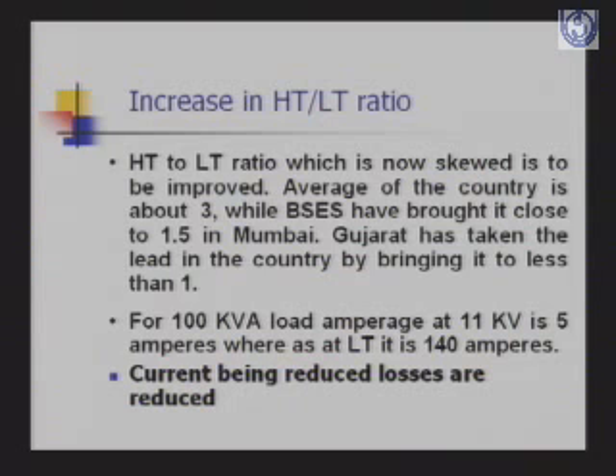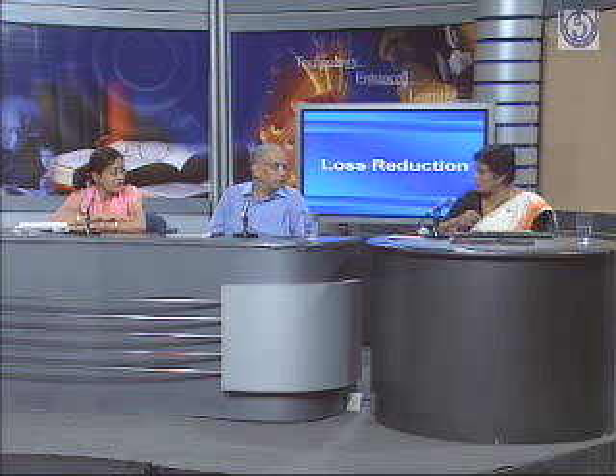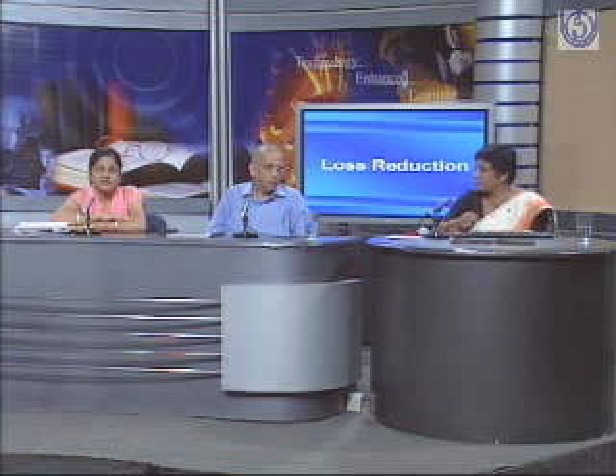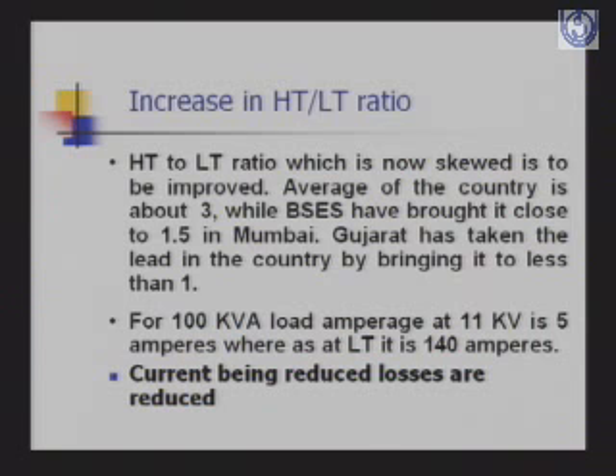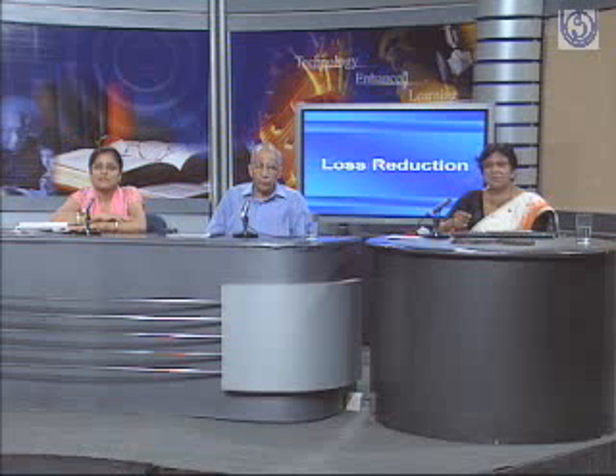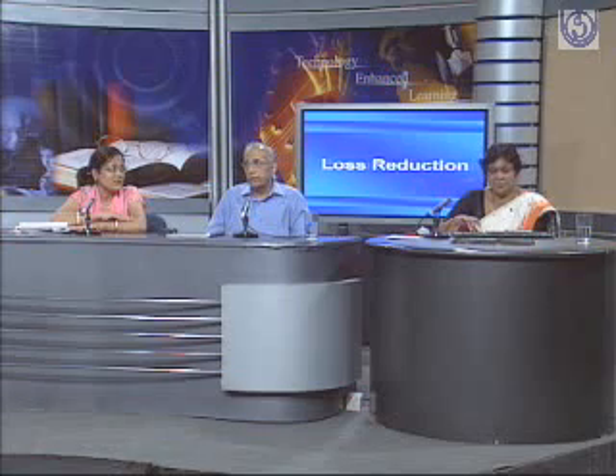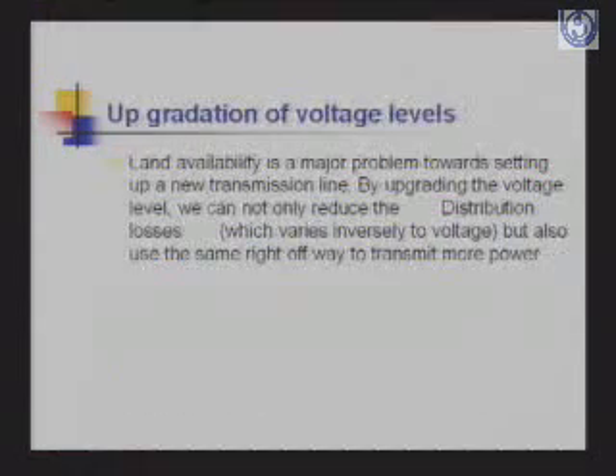For 100 kVA load, amperage at 11 kV is 5 amperes, whereas at LT it is 140 amperes. So this ratio is LT to HT. So it can be HT to LT or LT to HT. No, LT to HT can be high, if LT is more. Yes, then it will be the reverse in HT. So in your slide you are showing 3. Yes, okay. LT to HT is 3 times. That is what I said.